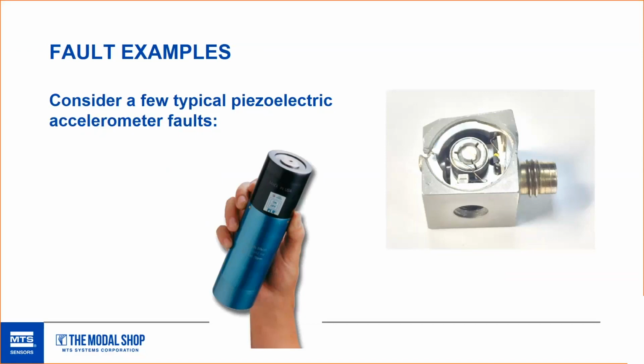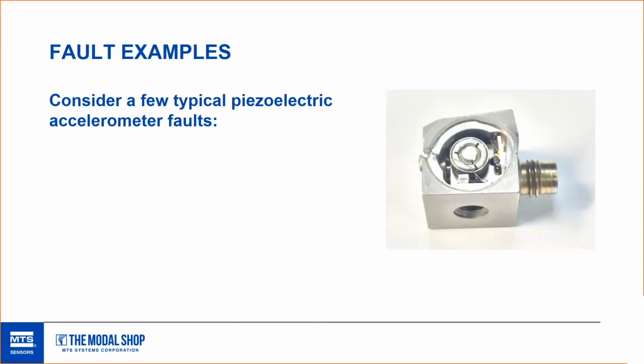So damaged piezoelectric crystals generally occur from shock damage to the sensor during a test or in handling. It can affect scaling, cause frequency shifts, and really it's not often found with a handheld calibrator. Often the damage is done quite higher, and we'll show an example of that in a bit.